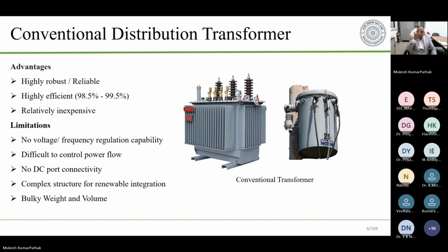So it's only about a 10% reduction, primarily driven by the improvement in the material. But the transformer which weighed 10 ton now weighs about 9 ton. So even though there is a reduction, it is not such a dramatic reduction that it can be counted as something which will revolutionize the use, installation and application of transformers. So the major issues are that its weight is very large, it occupies large volume, it does not have DC port connectivity, and there is no control of voltage and frequency.